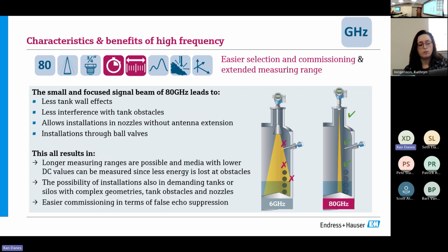It also makes things easier to specify, since I'm not as concerned with the tank wall effect. If I keep my signal tight, I don't have to worry about losing any usable gain to obstacles. But the other critical thing is if we've got hazardous or toxic materials, or vessels under pressure that can't go out of service, we can install in tall nozzles, or nozzles with one or multiple valves, to isolate from the tank.